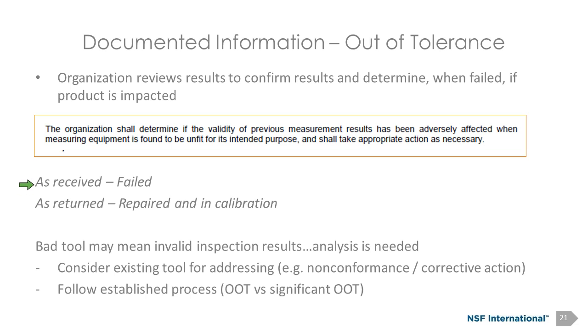Now if I send a caliper out and it's been adjusted by a 1,000th of an inch, and I'm measuring stuff that has maybe 30 thousandths tolerance, there's probably not a significant risk to my product. And that's where it gives us a little bit of leeway and says, as appropriate. We need to be able to demonstrate that we've done that review, that we've done some due diligence to ensure that that out of tolerance tool didn't impact product, and that action was taken against that tool and against the product that was impacted. So it's not just quarantining that potentially bad tool, it's doing some analysis against the product, the jobs, the historical devices that were measured by that tool.